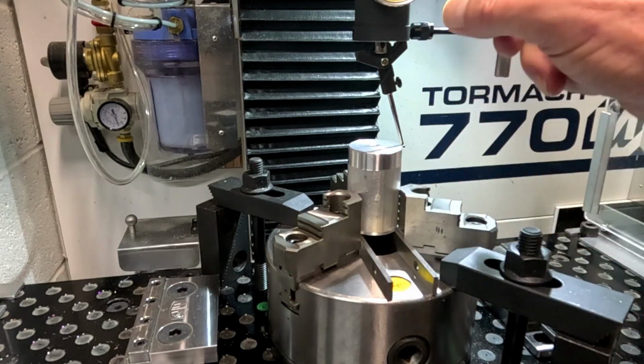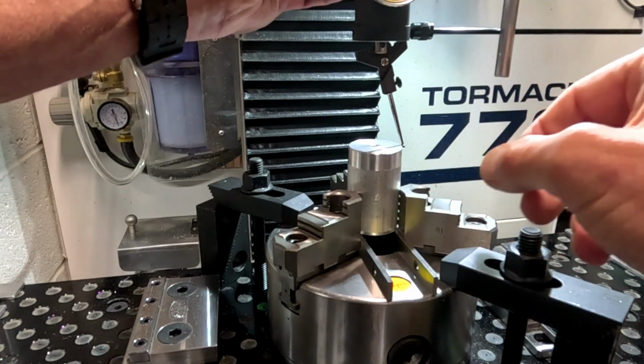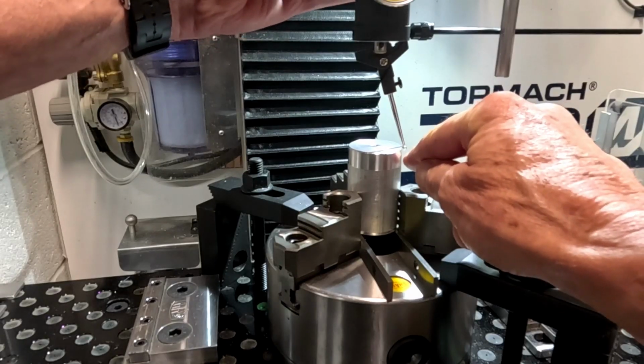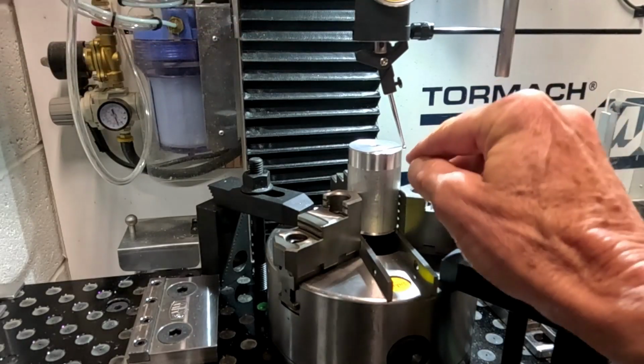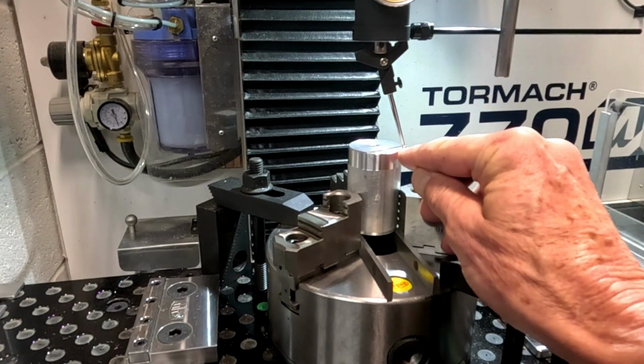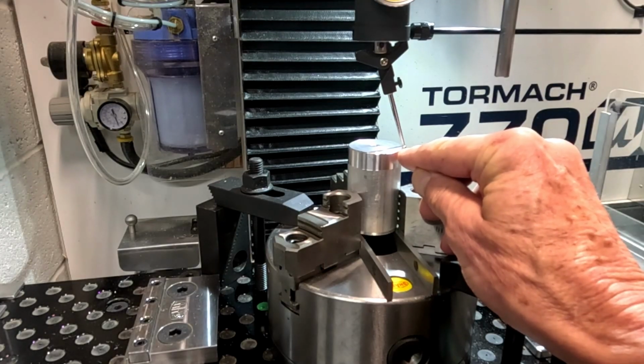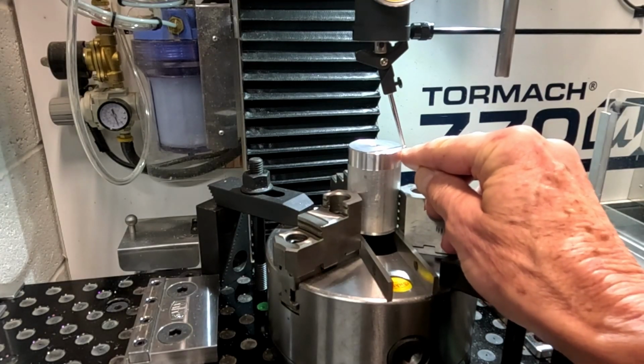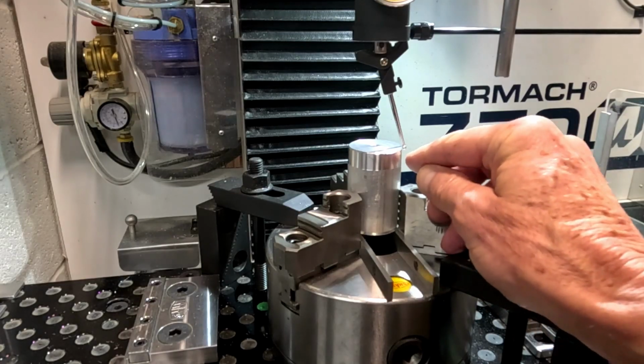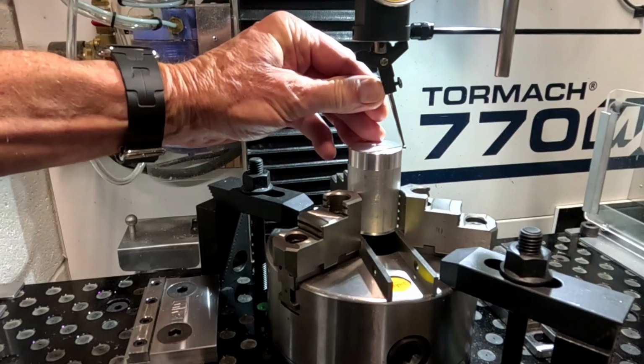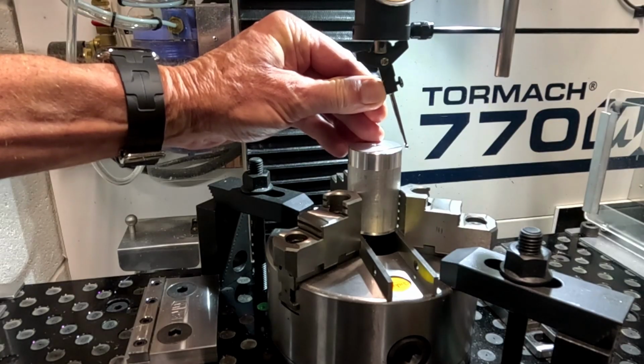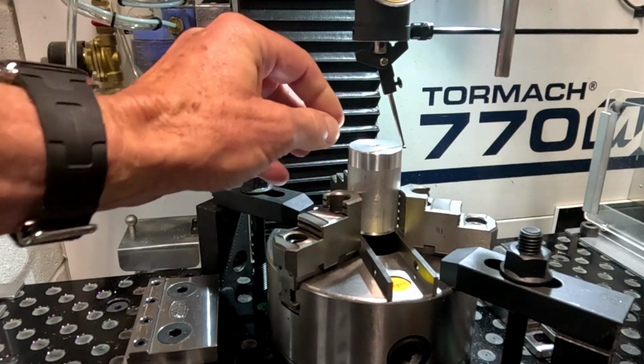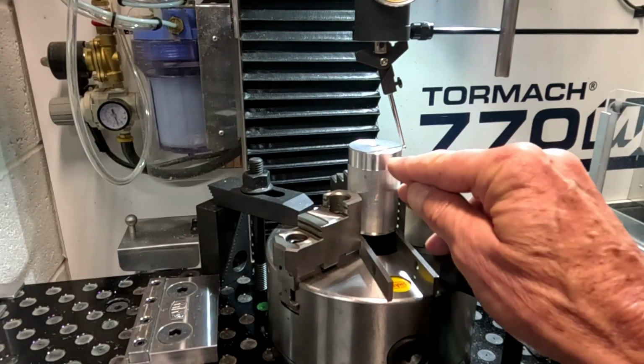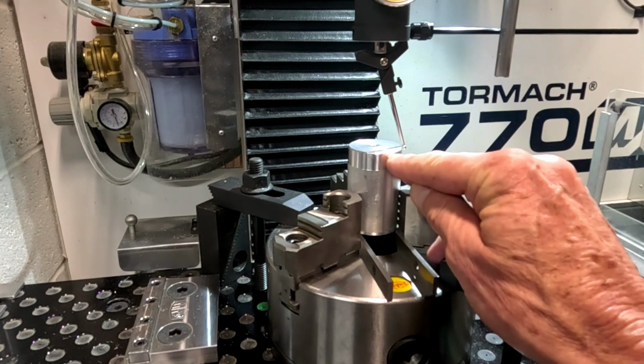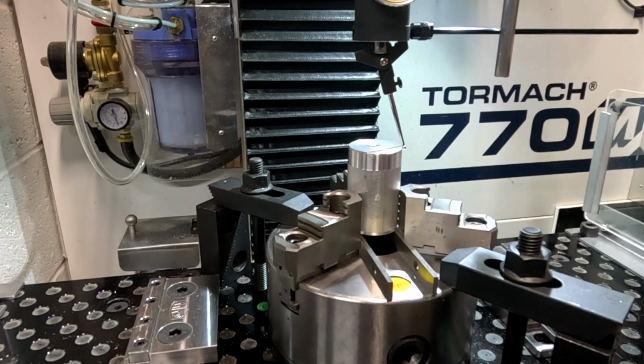You have to make sure that the ball at the bottom of the probe touches the outside diameter and not the little taper here, which it does, and that you still have deflection. It cannot be so tight that it rubs. So I checked it, there's a tiny little mark when it runs around. It's just below the taper, so it works in the setup.